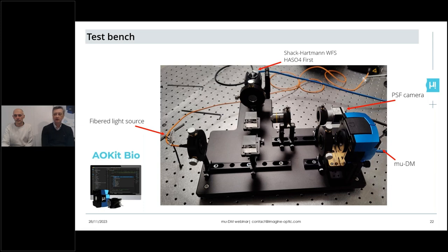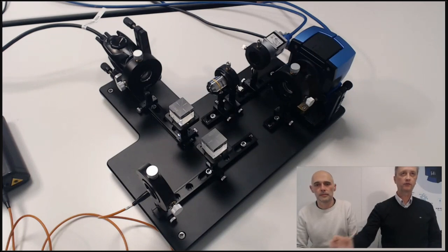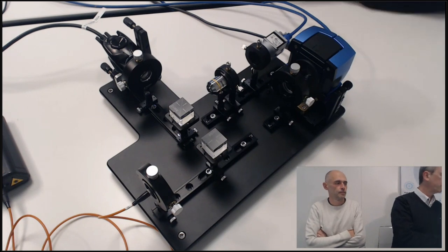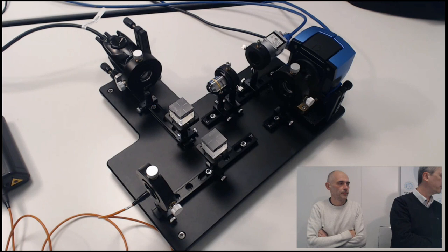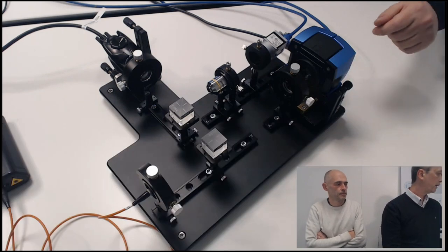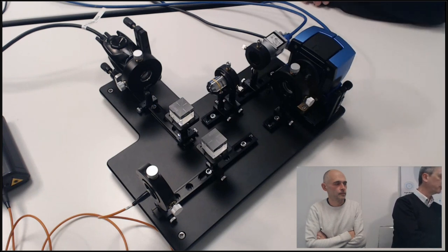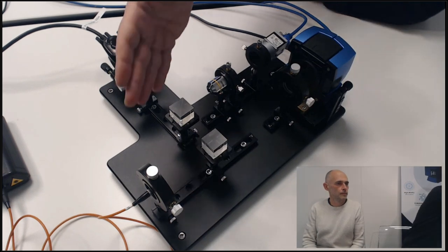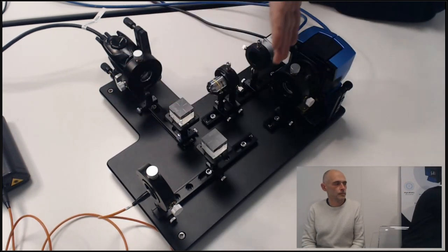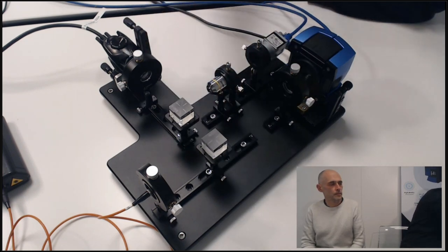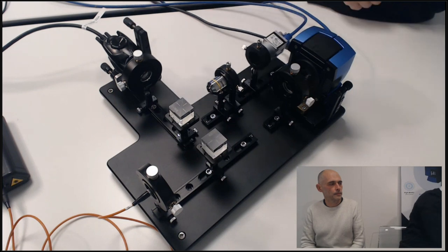Thank you very much, Fabrice. Let's start the hands-on part. I will start by introducing the optical bench we have here for the demonstration. We don't have a microscope today, but this bench will be able to show all the capabilities of the deformable mirror. We have mounted the deformable mirror — the MuDM — connected just with a USB 3 device and a small power supply. Basically all electronics are here with no additional boxes or bulky devices. We also have the wavefront sensor and a light source providing a slowly diverging beam which is collimated onto the deformable mirror, and the reflected light goes to the Shack-Hartmann wavefront sensor — both are conjugated to each other.